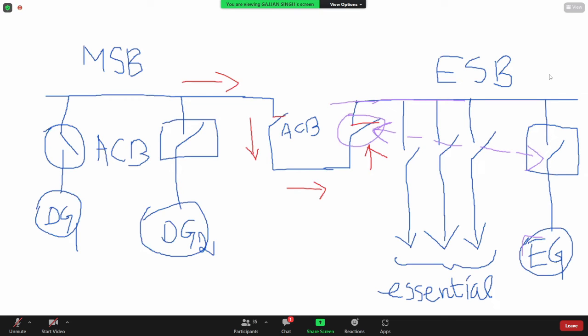See, learning is very easy, but holding that knowledge is difficult. For that, you have to make some notes, keep it somewhere. So I'm making a very quick run through what we have done up till now. Line voltage, phase to phase, is 440; merchant ships are 440. Done. Phase voltage, on shore, is phase and neutral. On a merchant ship, there is no neutral, so we step down. There is a transformer for 230. There is no neutral.